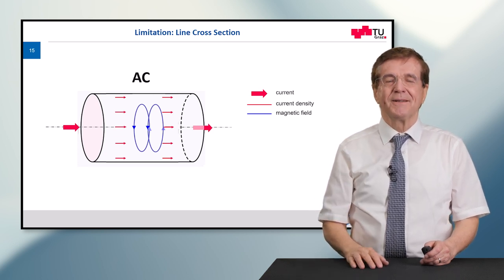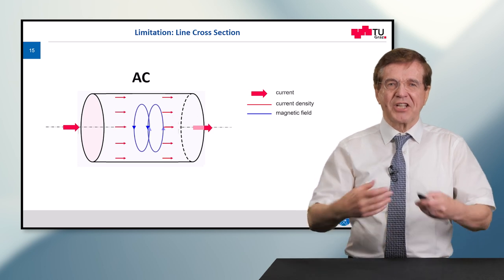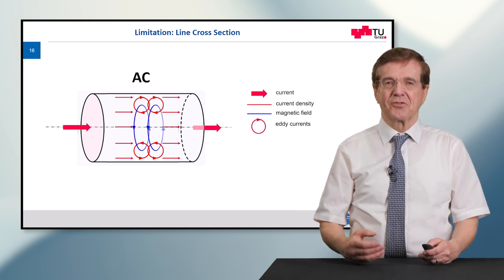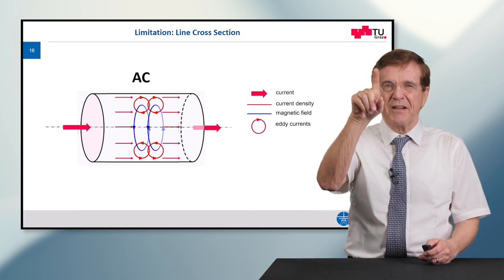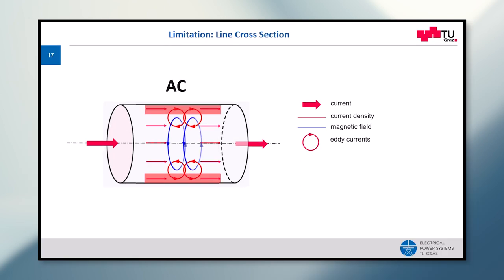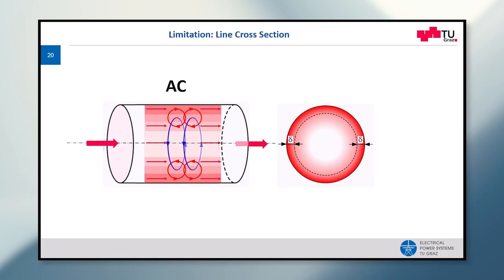Now when we come to AC, this electromagnetic field changes and it generates the so-called eddy currents, which are given as little red circles. And if you watch carefully, for example at the top of this drawing, you see current flow. So this means altogether the current density is high at the outer fringes and is low at the center of such a line.